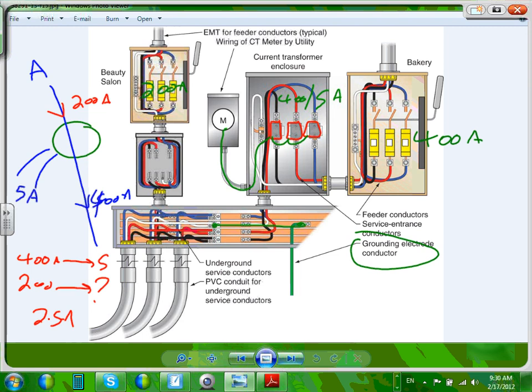So if you have 200 amp going through the system because you're not loading the system, you get 2.5. So what it does, it takes a very high amp and reduces it to an acceptable measurable value. Otherwise, you're going to burn the equipment, or your coils inside the meter would have to be so huge. So simply it's a kind of protective device. It's really not a protective device. It's a converting device. It converts very high amp to very low amp, so you can sense it safely and economically.